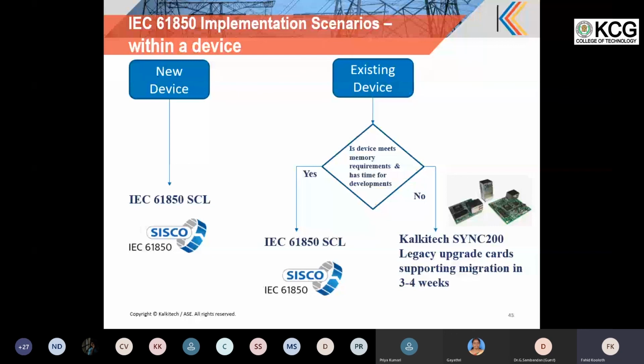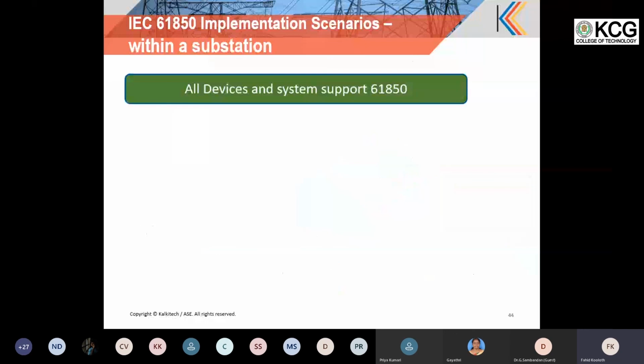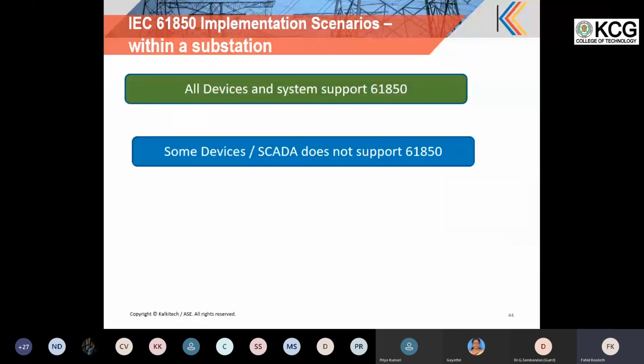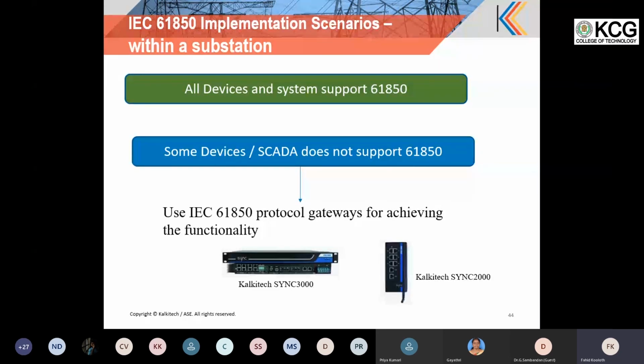Then system level migration: if all devices support 61850, you can use them directly. If some devices support 61850 but others do not, use a protocol gateway or something similar to achieve this functionality. So that is how 61850 implementation is currently adopted. With this, I come to the end of the two sessions, and I hope you got a basic idea of the 61850 standard.